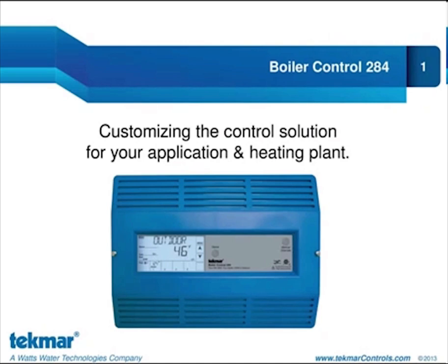The Boiler Control 284 is designed to operate up to 4 boilers to accurately maintain a target water temperature. The 284 operates any combination of condensing and non-condensing boilers that are either modulating, single-stage, or two-stage to provide a flexible and cost-effective mixed boiler plant solution with better system performance. As a result, it can be applied to a variety of different applications and heating plant designs. The wiring and the settings are what will allow you to create a more customized control solution.